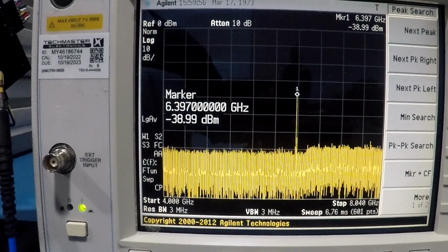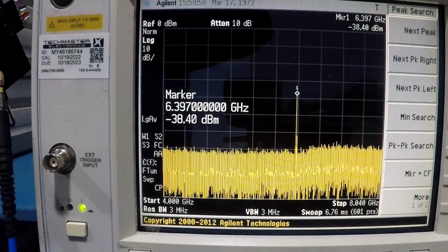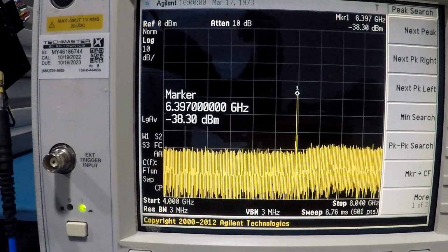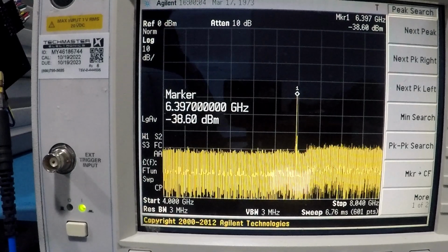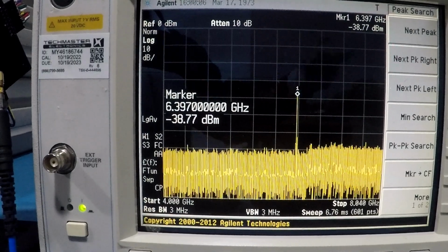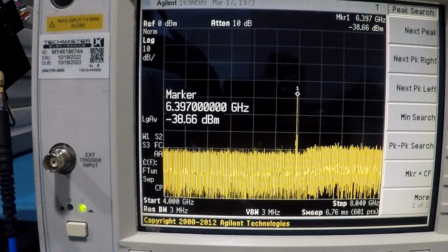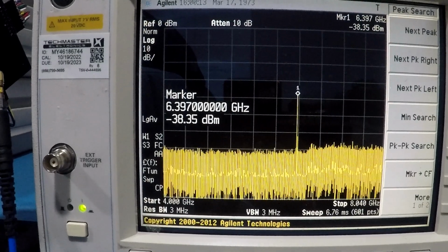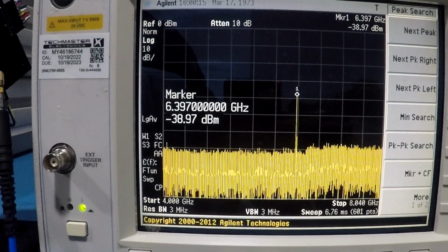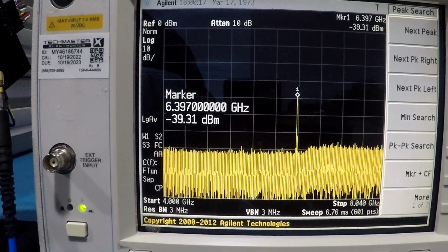The second data point it has. This is where I initially made the mistake though, because I was wondering if it's still picking up 5.4, because I forgot I had it set for multi-band instead of individual frequency points. So same thing, we'll go ahead and change it to 6.4.